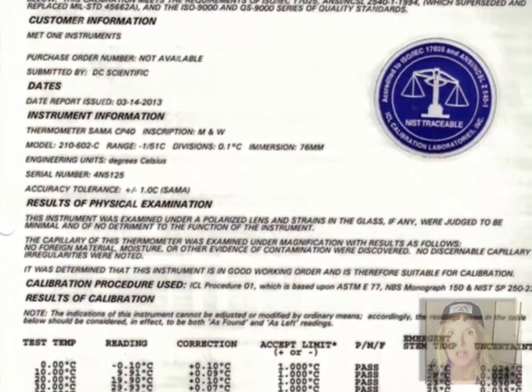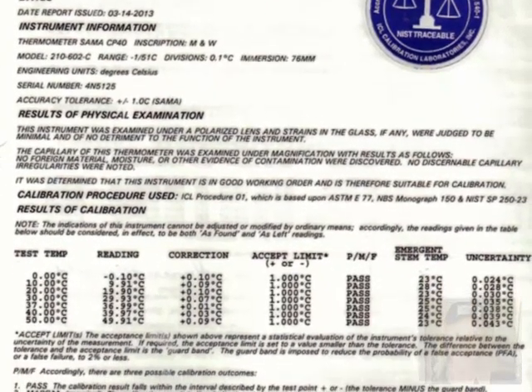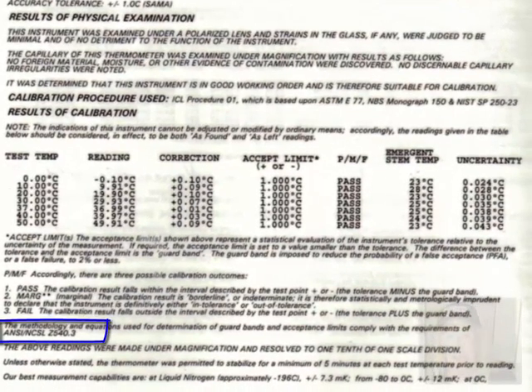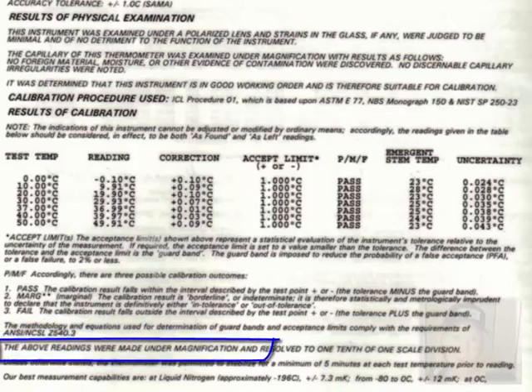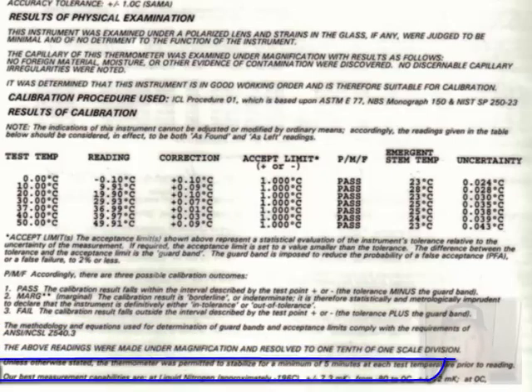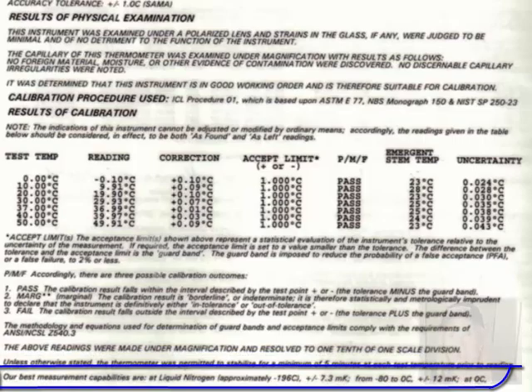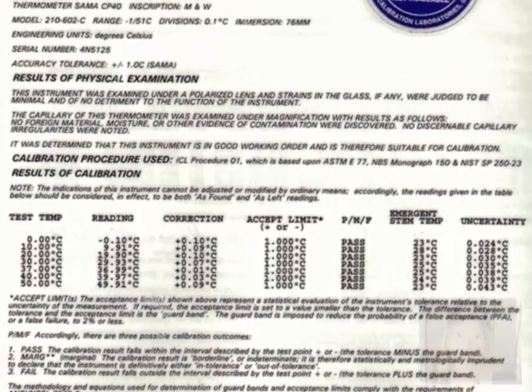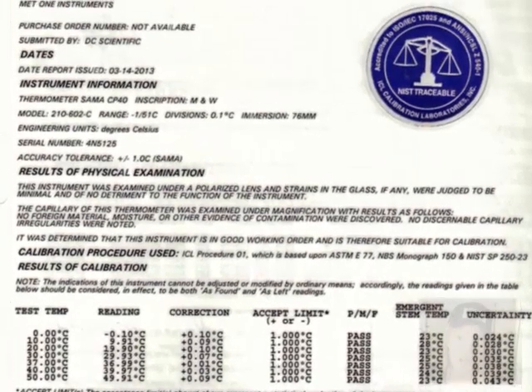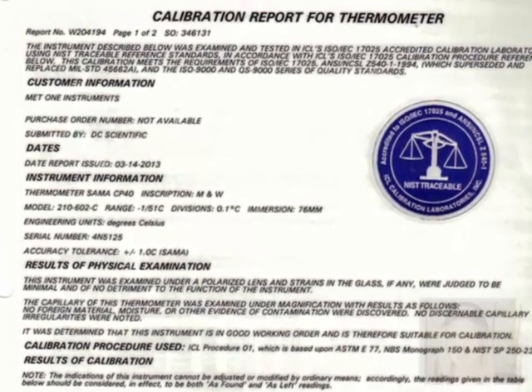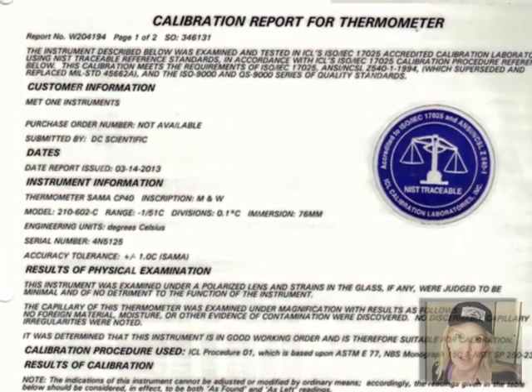And the certificate shows that they are operating within parameters, that they've been calibrated, and what standard the calibrating authority, like the manufacturer or the weights and measures laboratory, is using to calibrate your field instrument. And generating that certificate is called certification. So that term is usually used with your transfer standards, talking about how often they need to be recertified.